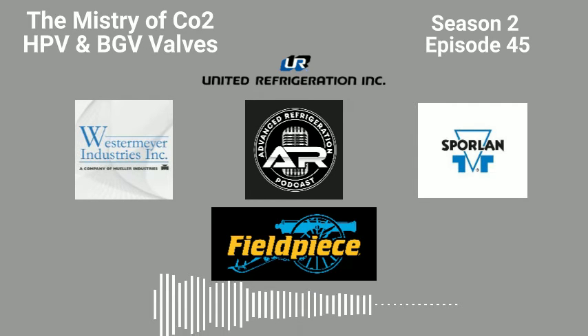Okay. So now we start adding these two valves together. So you got one valve opening, one valve closing constantly, one valve closing, one valve opening. So as the flash tank bypass valve closes down a little bit, the pressure starts dropping, the high pressure valve starts opening, to start filling the tank up more and keeping the pressure up. So these two valves have two different PID loops that are working together. So they're constantly looking at two different things.